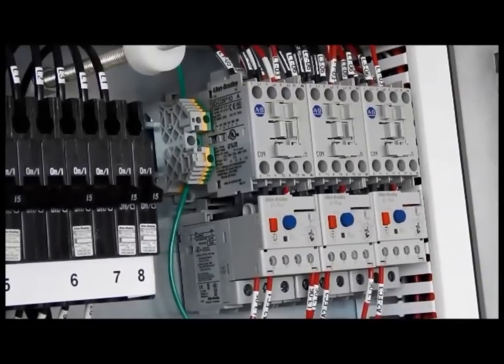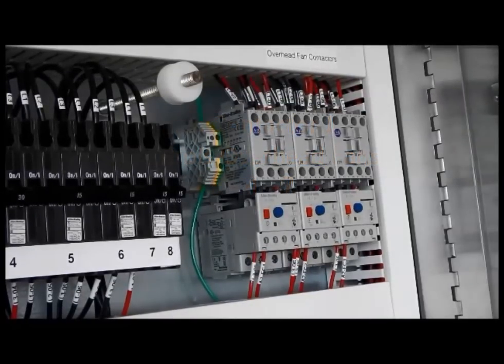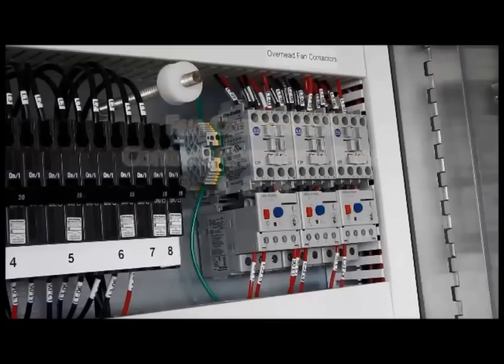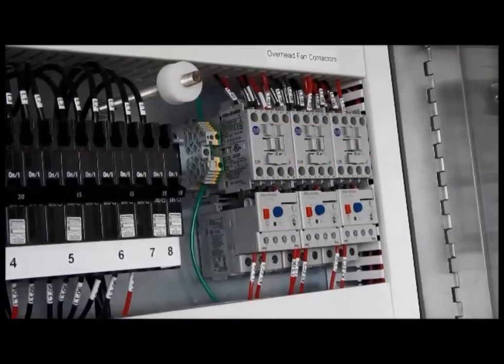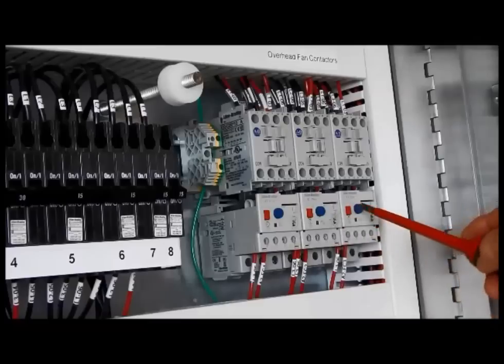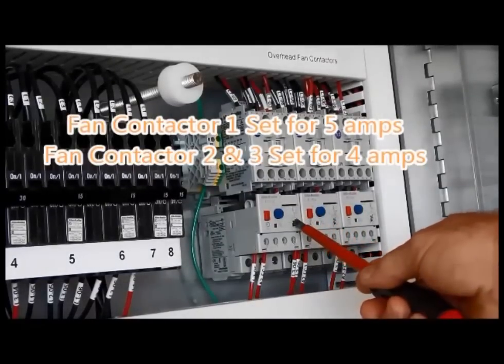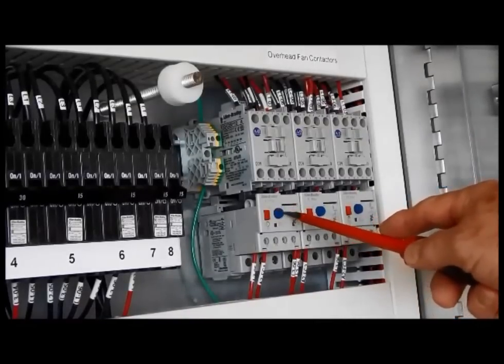To the right of breakers 1 through 8, we have what we call the fan controls or fan contactors. The one on the left is contactor 1, which controls overhead fans 1 and 4. The middle overhead fan contactor controls fans 2 and 5. The third controls overhead fans 3 and 6. You will notice on these contactors that the bottom section is an overload with a dial that can be moved to adjust the amperage the unit is looking for. Typically, contactors 2 and 3 are set at 4 amps and contactor number 1 is set for 5. There is also a blue button to test the unit and a red button as a reset.